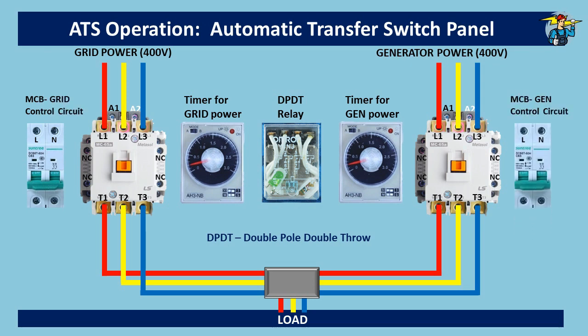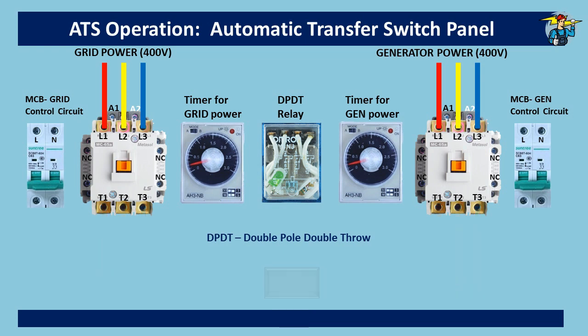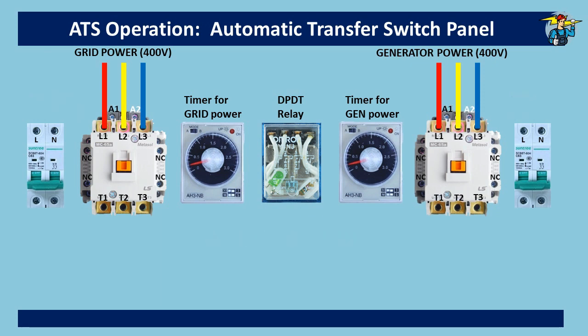Although three-phase power from grid and generator is shown here, you can also wire a single-phase 220-volt generator for the load when grid power is from a single-phase 220-volt supply. For this, connect phase and neutral wires to any two ports on the main contactor and keep the remaining port of the contactor empty.